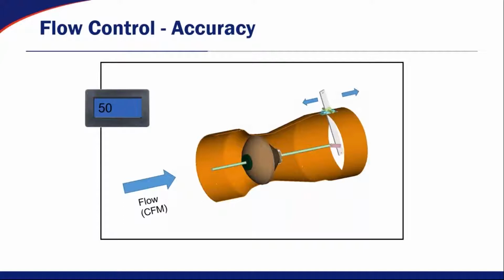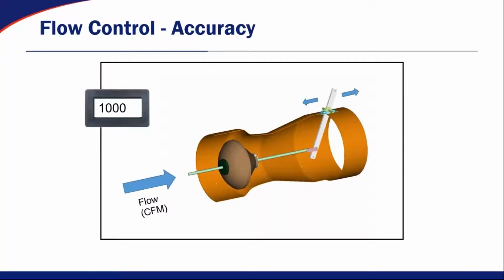Now, taking into account that 48-point flow curve that I mentioned earlier, now that we can take the differential pressure out of the equation, we can look at the position control of the valve in a completely separate control loop than what you would have if you were trying to measure flow and control that valve based on the varying differential pressure through the valve. So now that we know the pressure is taken out of the equation, you can easily position the entire drivetrain of the valve based on that 48-point characterized curve. And that's going to give you not only a quicker speed of response because you're going to a known set point, but it's going to be 100% repeatable, and we can guarantee that our valves don't hunt trying to find their set point due to changing duct pressure conditions.